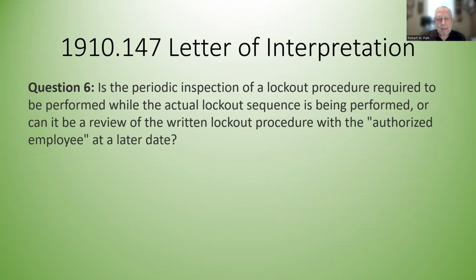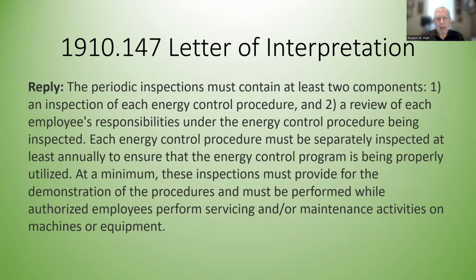Question 6. Is the periodic inspection of a lockout procedure required to be performed while the actual lockout sequence is being performed, or can it be a review of the written lockout procedure with the authorized employee at a later date? Reply: the periodic inspections must contain at least two components. One, an inspection of each energy control procedure, and two, a review of each employee's responsibility under the energy control procedure being inspected. Each energy control procedure must be separately inspected at least annually to ensure that the energy control program is being properly utilized.